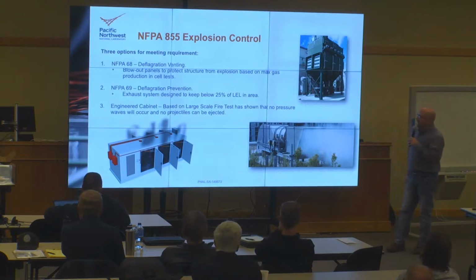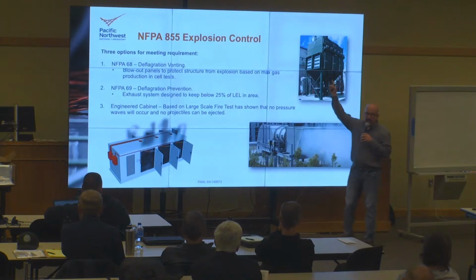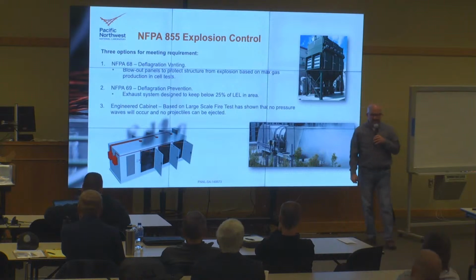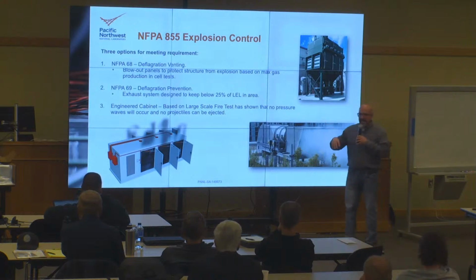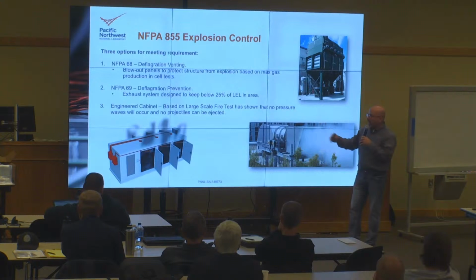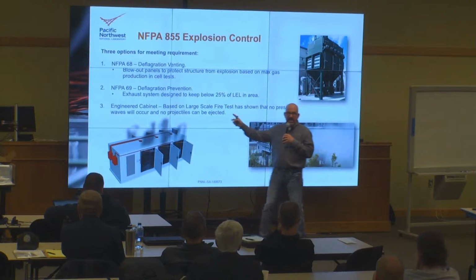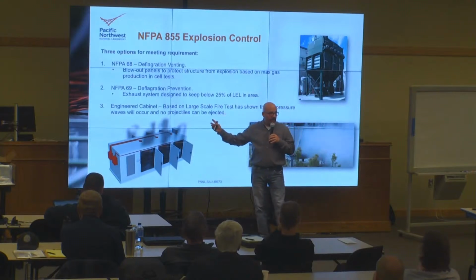So the first one is NFPA 68, deflagration venting — pressure relief panels. The next one is deflagration prevention per NFPA 69, some kind of exhaust system that will keep the gases below 25% of the lower flammability limit. And then the third option is some performance-based design, an engineered cabinet that will not allow pressure waves or projectiles to be ejected, based on the large-scale fire test. It has to be evaluated during that test.